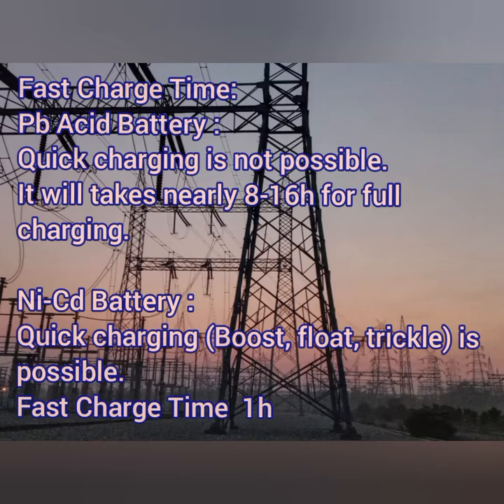Next is fast charging time. For lead acid batteries, fast or quick charging is not possible — it takes nearly 8 to 16 hours to fully charge. Also, whenever discharging exceeds 40 percent, the battery must be fully charged; using a lead acid battery with partial charging will reduce its efficiency. Nickel cadmium batteries can be quick charged or trickle charged — full charge can be achieved within about one hour.